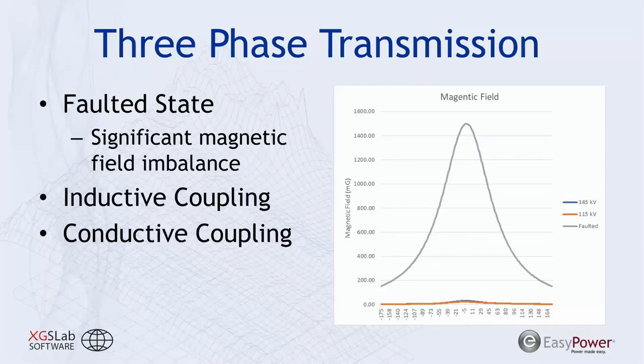In a situation where you have a fault, you end up having a significant phase current imbalance, which results in significant magnetic field strength from one of those phase conductors. And that's going to result in a much more significant inductive coupling as well as conductive coupling occurring during a faulted state, and that can dramatically affect the induced voltages and conducted voltages on your recipient object.